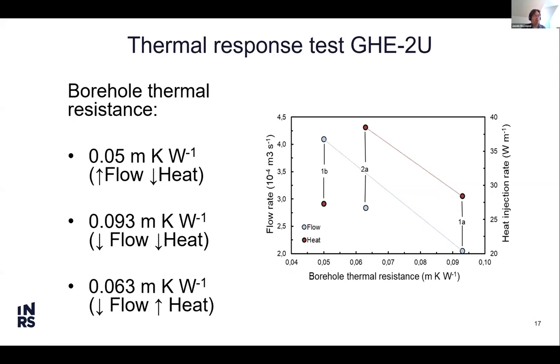So those systems, I think, with open hole and groundwater filling the hole, have good potential, especially for cooling. Because in cooling mode, for systems that you would expect in Colombia, for example, you're going to inject heat in the ground and you're going to start to have free convection in your borehole. So that's good. But those systems need to be operated at a high flow rate that decreases the thermal short circuiting. The flow rate has an impact on the thermal short circuiting between the pipes, and the higher the flow, the lower this thermal short circuiting, and the more you can decrease your borehole thermal resistance to actually have an impact on the borehole length needed for your system.